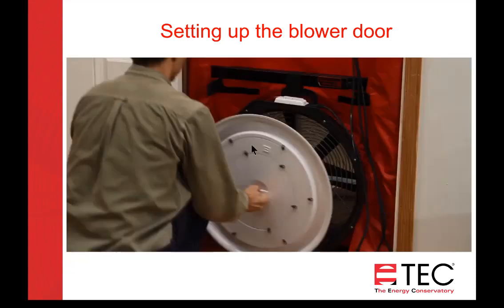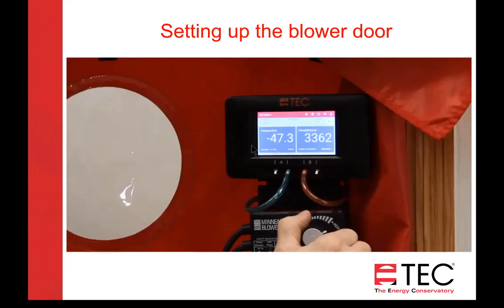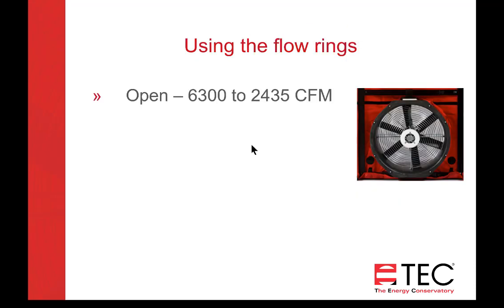Okay, so next we'll take the rings off, and we'll turn the fan up to close to 50 pascals. And we've got it in the flow at 50 mode, so it'll display the flow on the right side there. Using the flow rings, the open ring will move between 2435 and 6300 CFM.